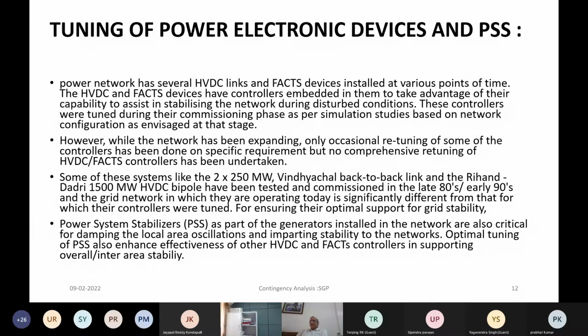In the same way, yesterday we also mentioned that in the excitation system we have power system stabilizers. Depending on the inter-area oscillations which are experienced, the power system stabilizers can be effectively tuned to help damp those oscillations. And all these being dynamic devices, they need to be tuned as network changes happen. So periodically, these devices will need to be reviewed based on the actual system condition, so that the corrective action becomes more effective.